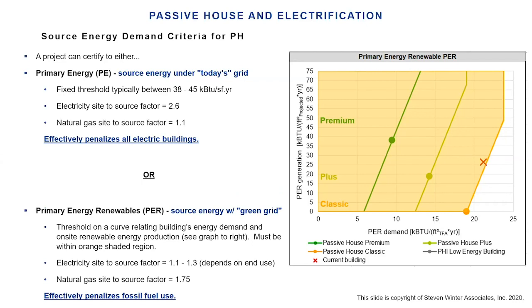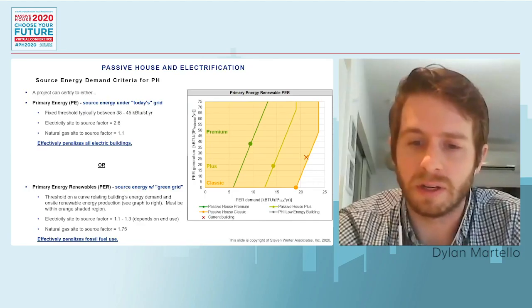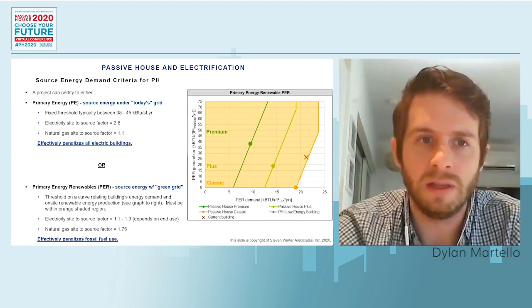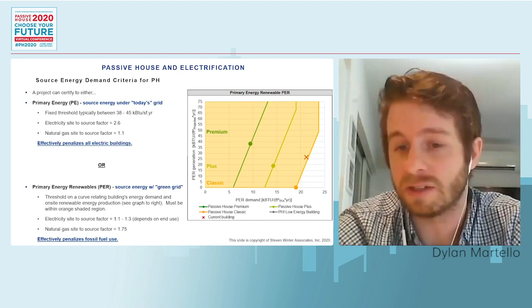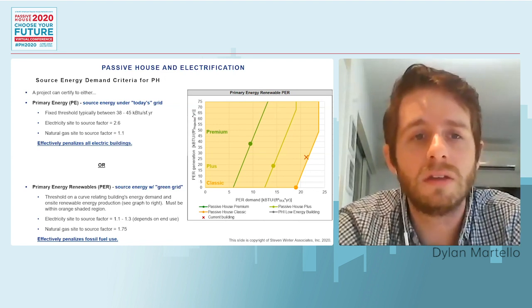When we talk about how this relates to building electrification, because this is ultimately what we're discussing, the decision on whether a building will be all electric and certified to the PHI standard will really impact which path is chosen here. The PE path, because of that site-to-source factor being 2.6, compared to natural gas being 1.1, essentially all-electric buildings can in effect be penalized under the PE path. So any project that's all electric, it makes much more sense to go under the PER pathway, because fossil fuel use is actually penalized a little more than electricity use. Keep that in mind.